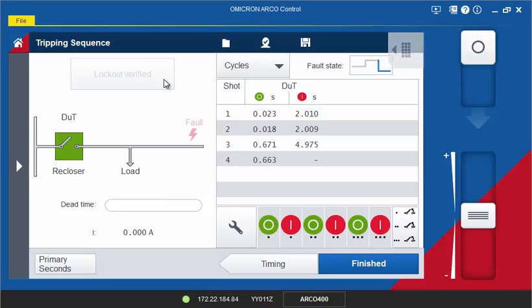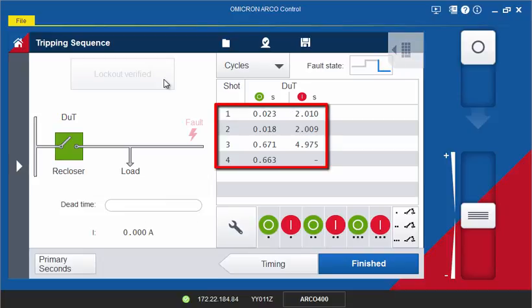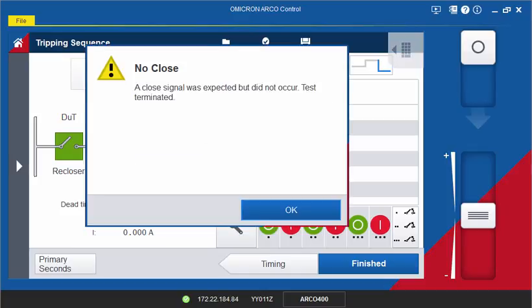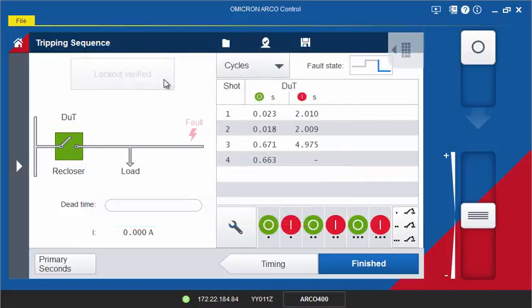The results of the test are displayed in the right half of the screen. You can see the trip time for the defined current output and the actual open interval time. If any of the previously defined timeout parameters are exceeded, a popup error will appear. Since a message has not popped up, the measured open interval times are within the defined tolerance.